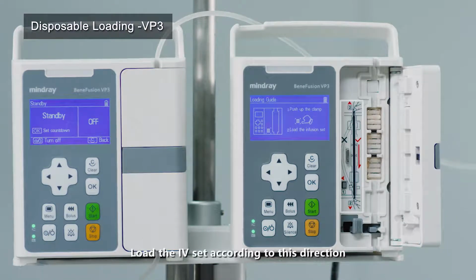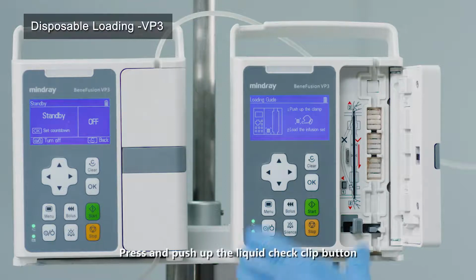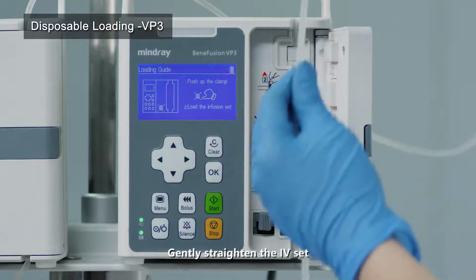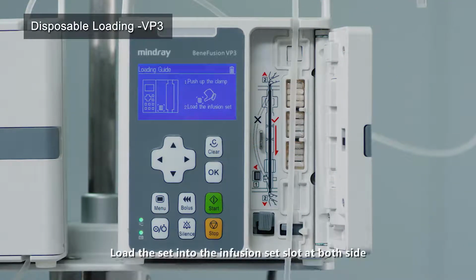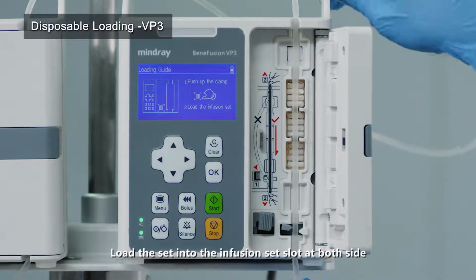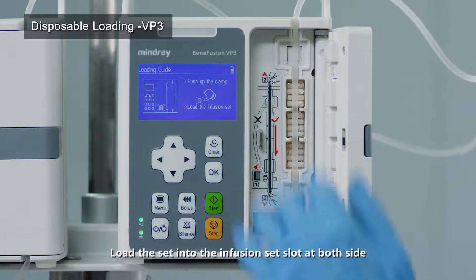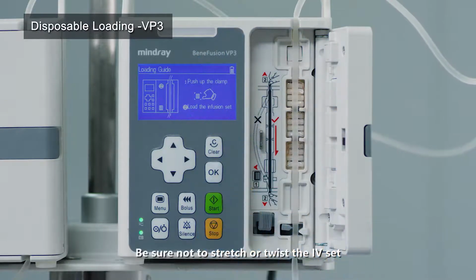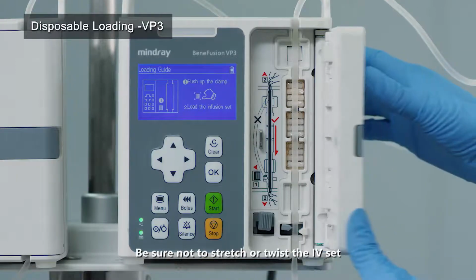For the infusion pump BeneFusion VP3, pull out the door latch to open the door. Load the IV set according to this direction. Press and push up the liquid check clip button. Gently straighten the IV set. Load the set into the infusion set slot at both sides. Be sure not to stretch or twist the IV set.